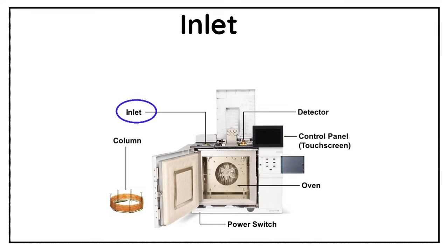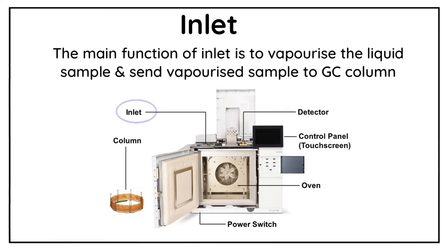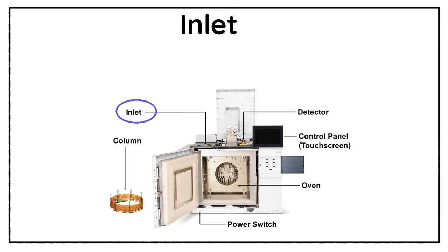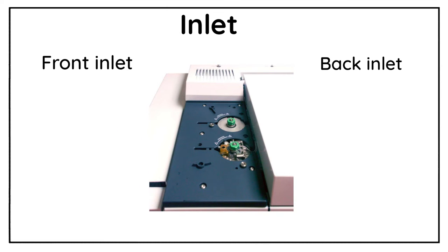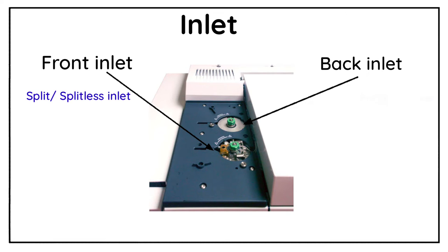Now comes the second part of the GC instrument which is called the inlet. The main function of the inlet is to vaporize the liquid sample and send the vapors of the sample into the GC column. Generally there are two inlets in Agilent make GCs, commonly called the front inlet and back inlet. Technically, the front inlet is called the split/splitless inlet and the back inlet is called the purged packed inlet.